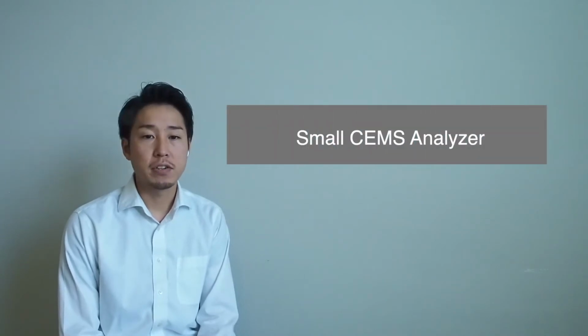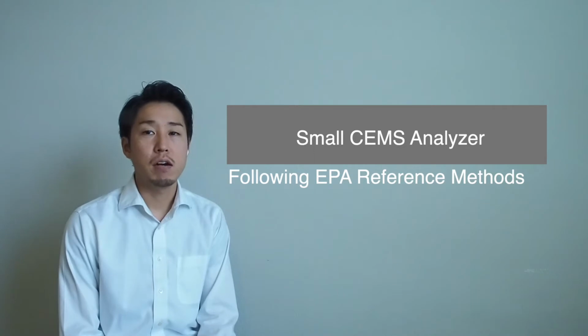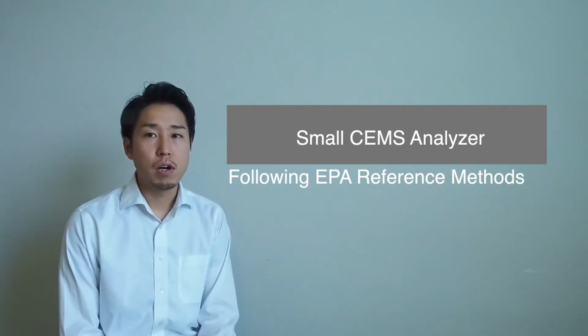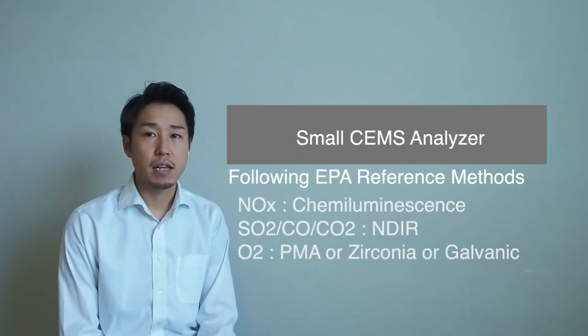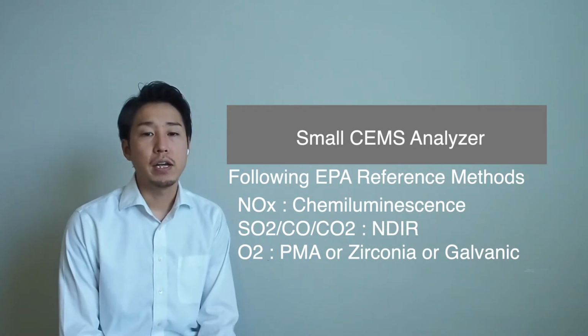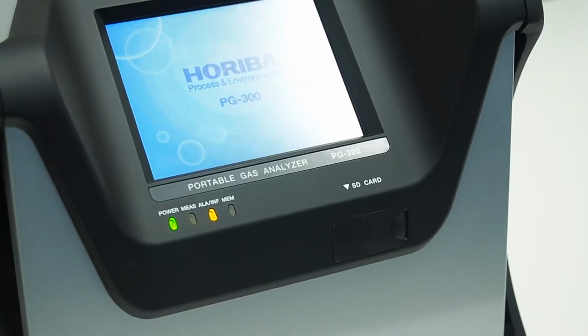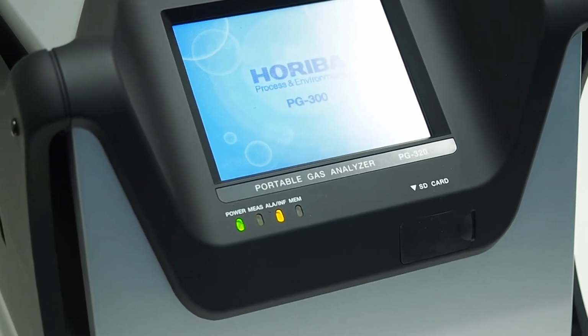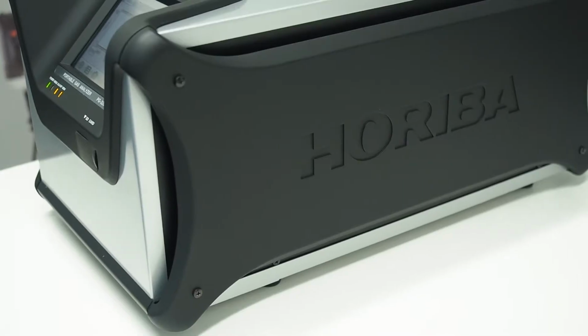Today I will give you a quick sales guide for the PG300 series, which is a portable gas analyzer. PG300 is a small CEMS analyzer following the EPA reference method. This is the only analyzer which has CLD, NDIR, SO2, CO, CO2, and three types of O2 analyzer. It can measure up to 5 parameters, and since it is so unique, still so many users are not aware of it. So I need your help to expose it to the market.